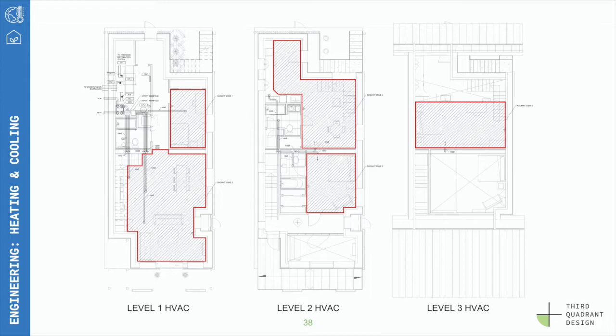During operation, a central controller receives temperature and humidity data from the thermostats and determines a set point temperature for the system. In cooling mode, floor surface temperatures may not fall below the dew point temperature of air in the space to mitigate condensation on surfaces. And in heating mode, floor surface temperatures may not exceed 29 degrees C to mitigate excessively hot surfaces.